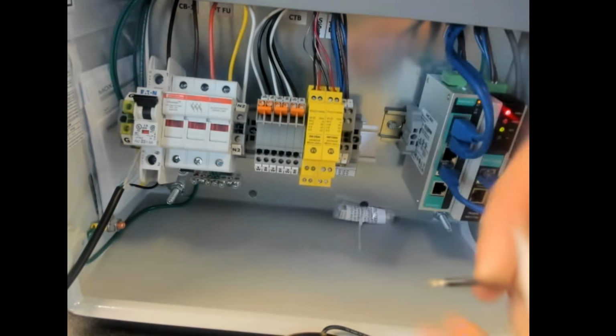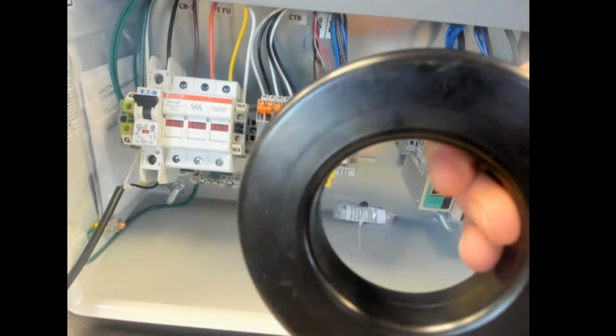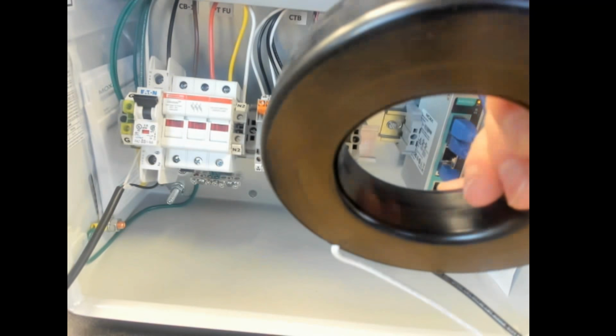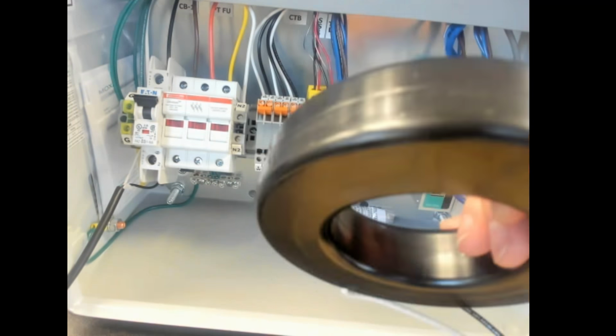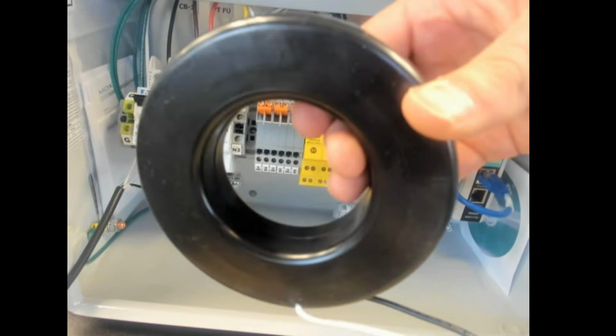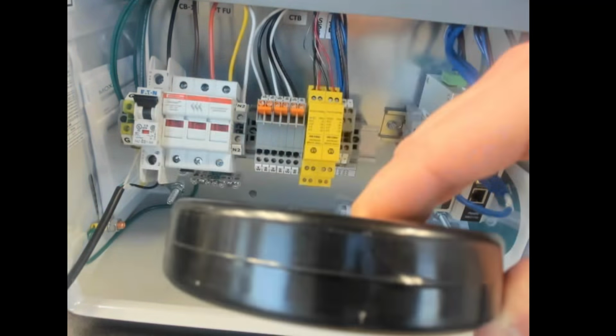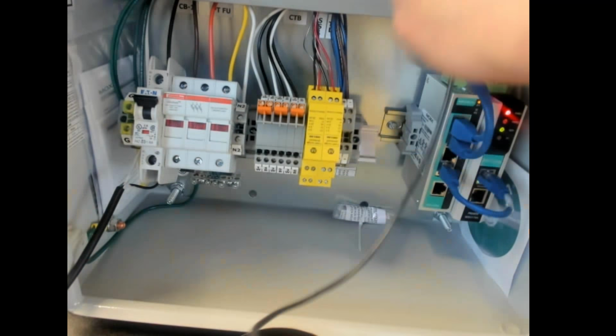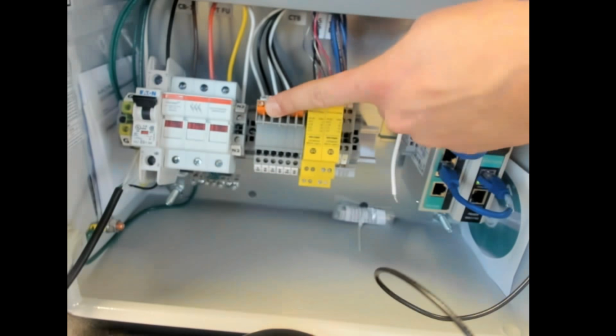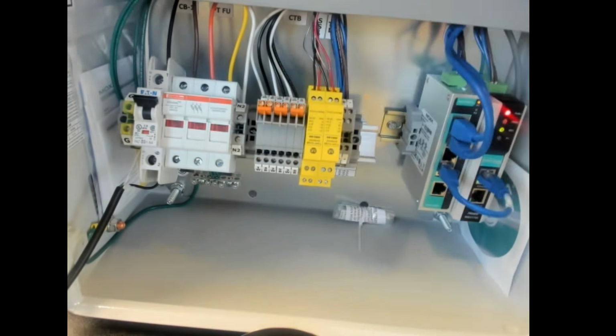Now, that's actually not a problem for the CT. The CT has no resistance. So it's going to be a short, but basically, as long as that flow keeps happening, the CT is fine. So it's intended to be that way. So if for whatever reason the electrician is working in here, they would likely keep the shorting tab in the up position, and that's how it ships.